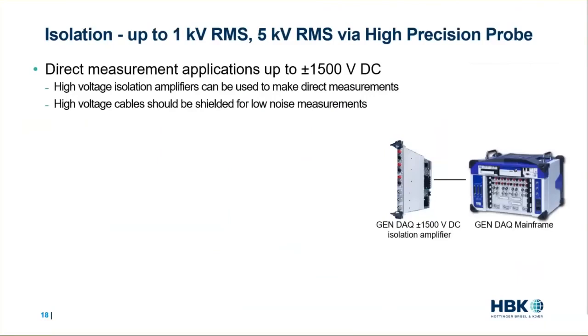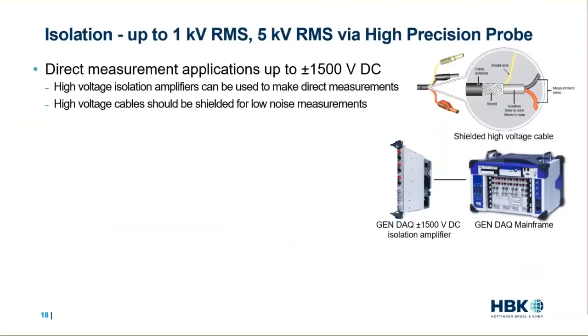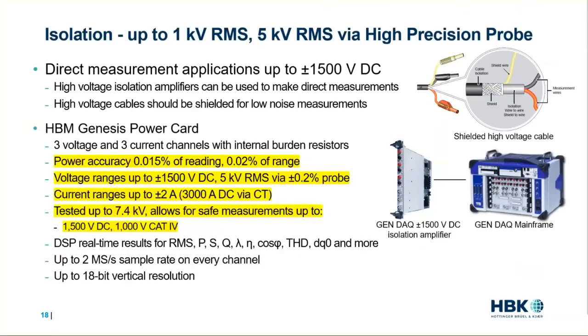So here's an excellent solution to directly connect and acquire high power signals in electric motor, generator, or electric grid tests up to plus minus 1,500 volts DC, or sometimes more, using this high accuracy and high bandwidth power card in conjunction with shielded high voltage cables for low noise measurements. Now, the power card has 3 inputs for voltage and 3 for current.